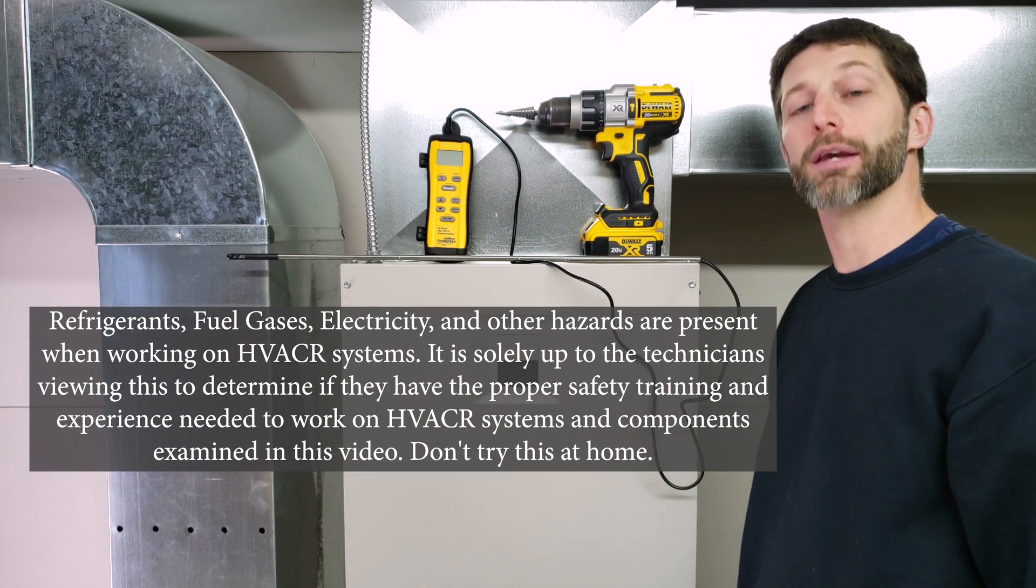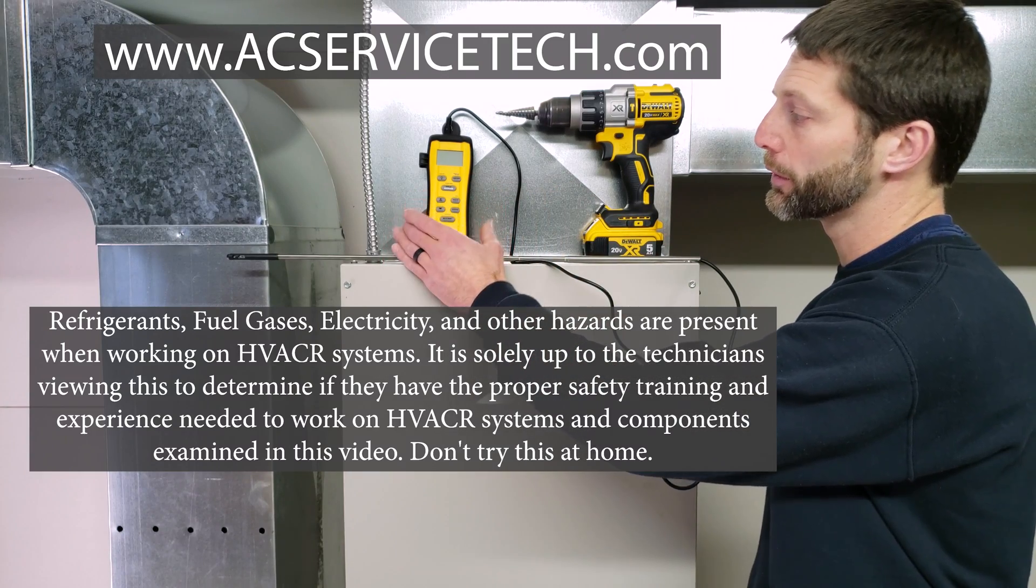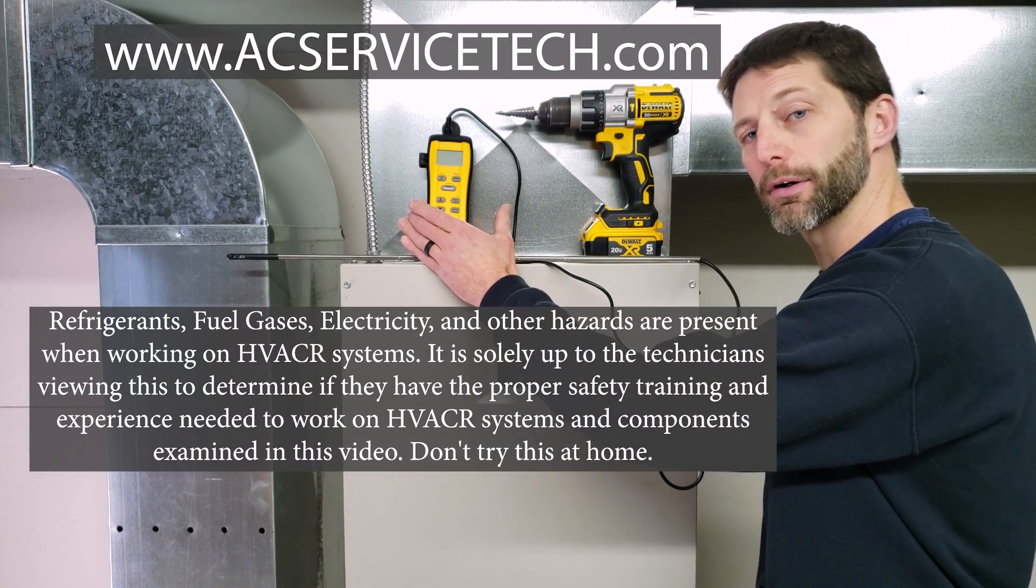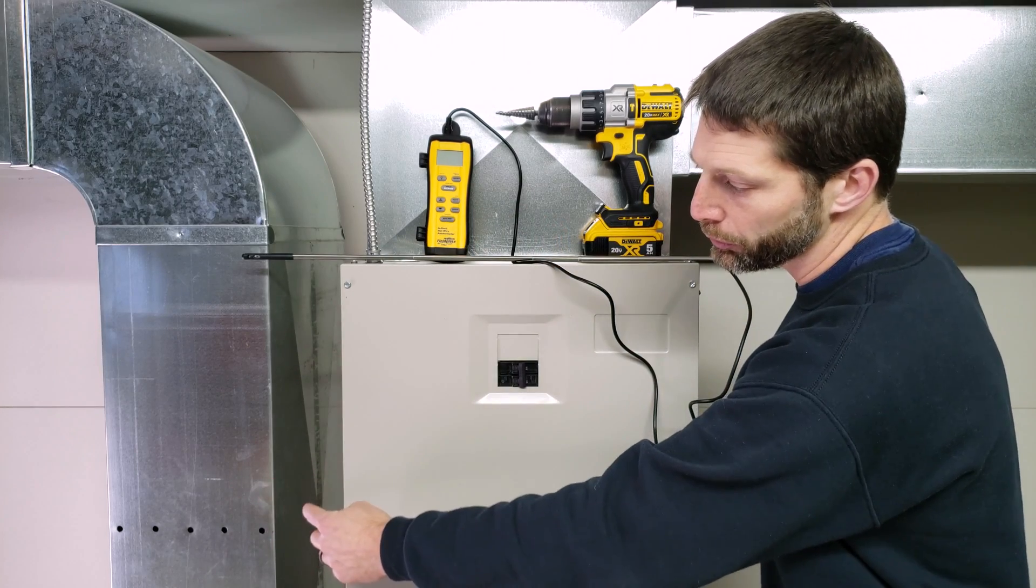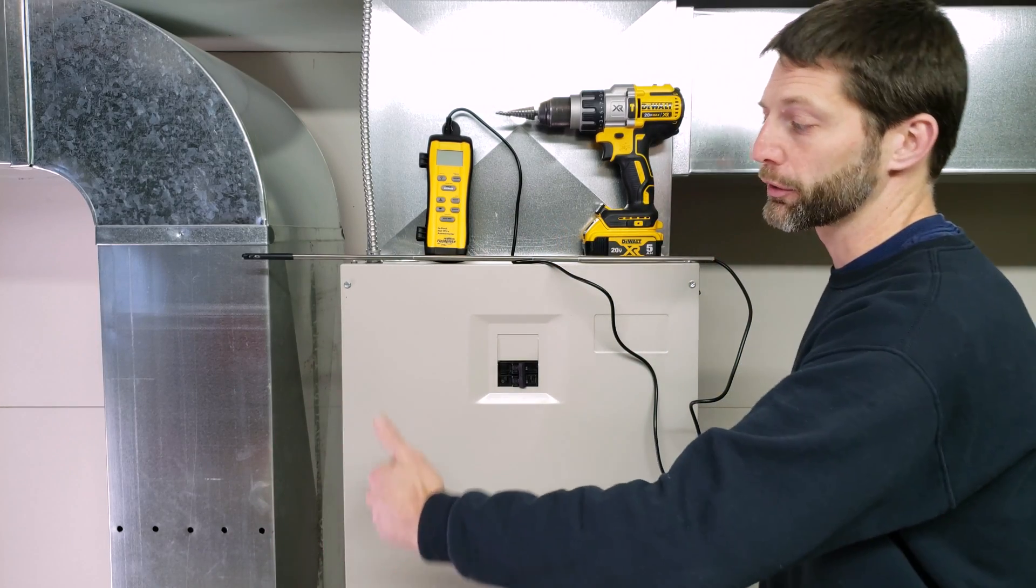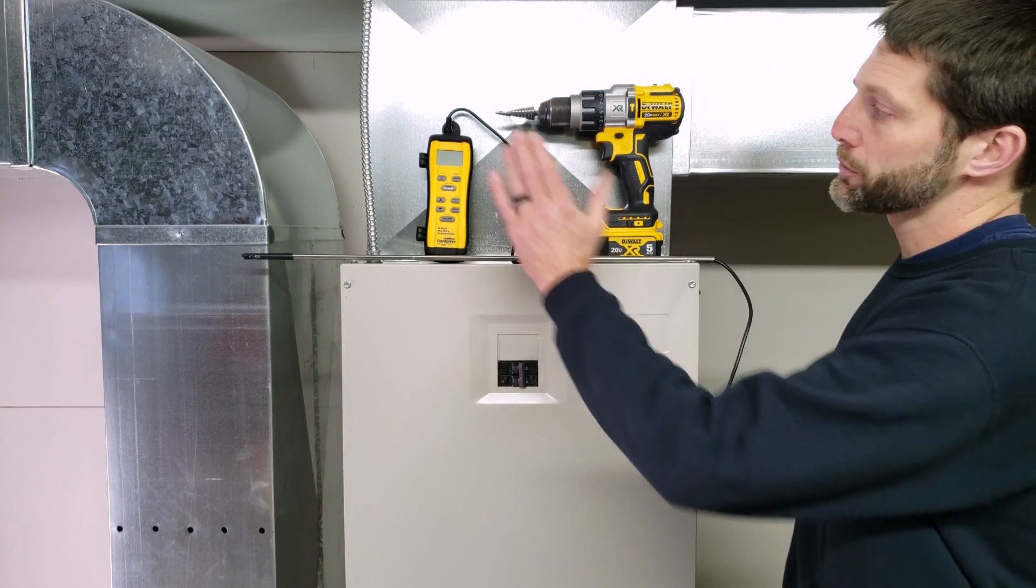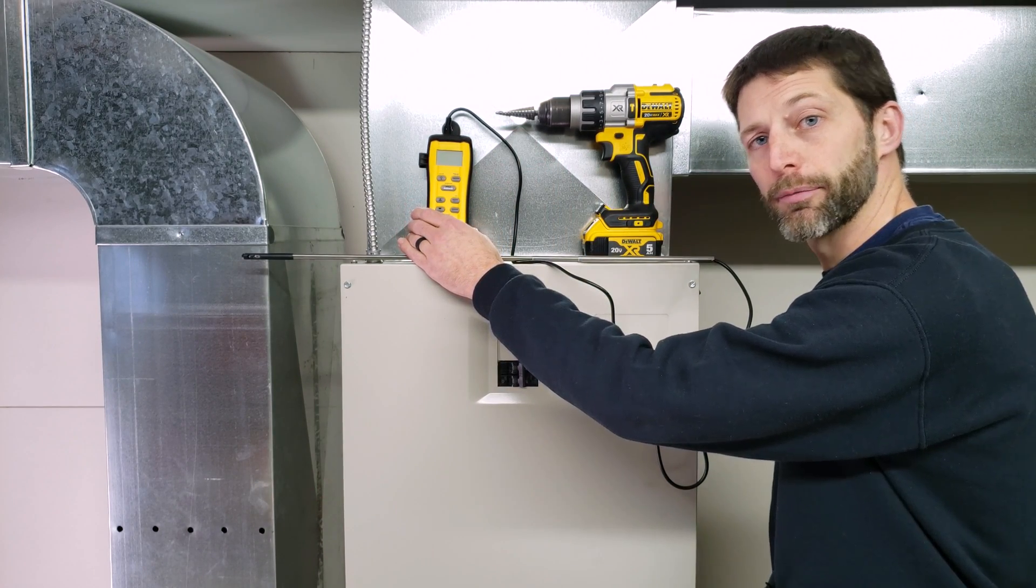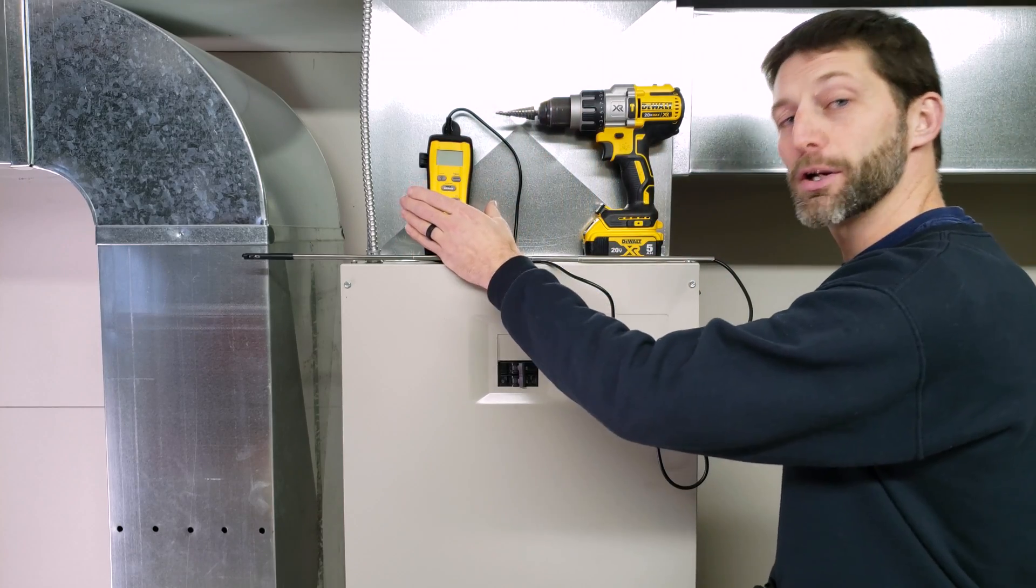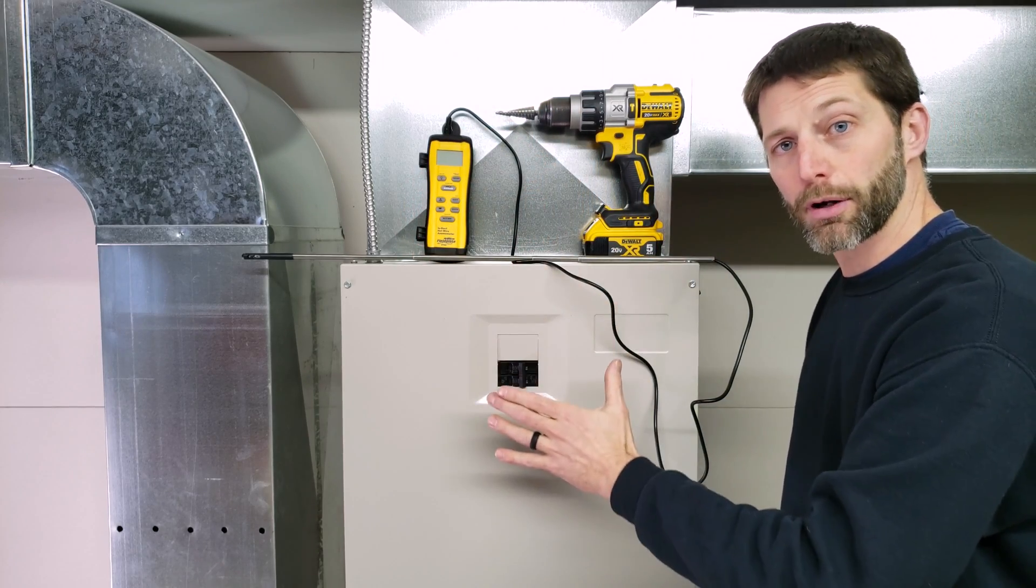Hey guys, this is Craig Migliaccio with AC Service Tech. Today we're going over how to measure airflow with an in-duct hot-wire anemometer. We're inserting this tip into the duct through pre-drilled holes, and we'll measure our airflow in CFMs (cubic feet per minute) and confirm our average CFM is correct using the temp rise formula.